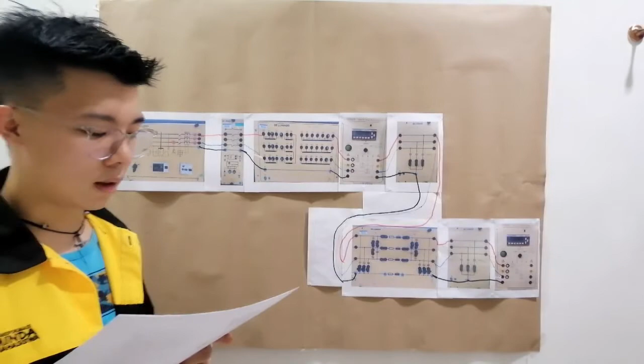We set the supply voltage to 380 volt, and measure the voltage between conductors at the beginning and end of each line capacitor, as well as the reactive power consumed, taking the data from the three-phase measurement meter.